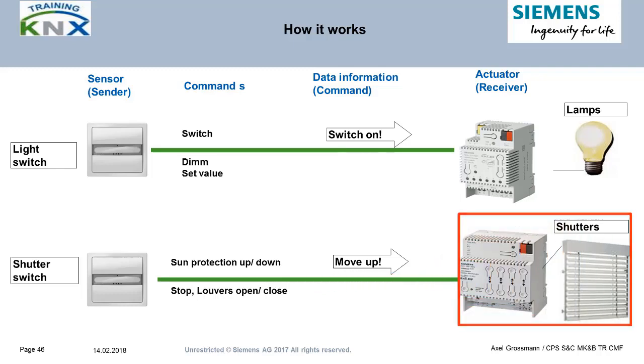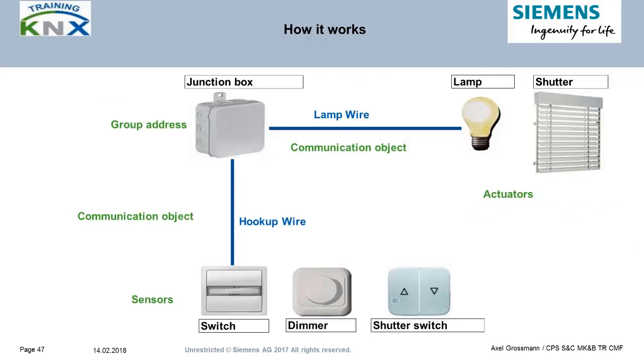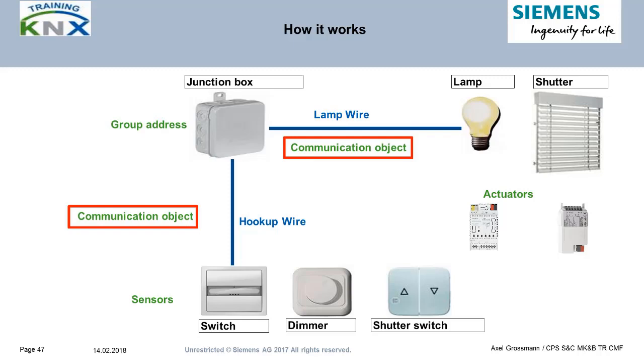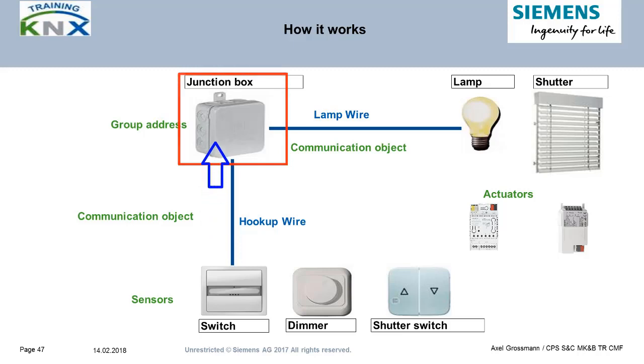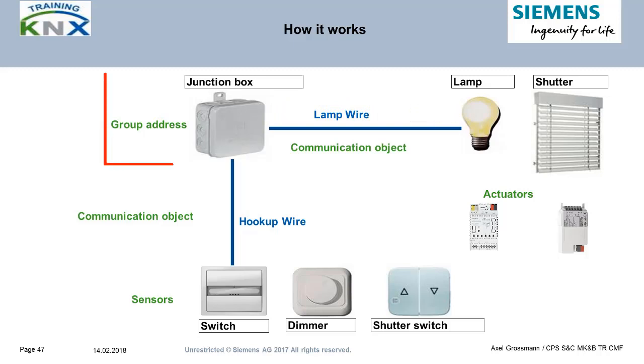Another example is blinds control. We now learn two important keywords: group address and communication object. The picture shows an analog sample from the traditional world of electrical installations — load and operation unit are connected via junction boxes. In these boxes, the hookup wire from the rocker switch meets the lamp wire on a screw or cage clamp terminal. In the KNX world, you might call the junction box a group address and the two connecting wires as communication objects.